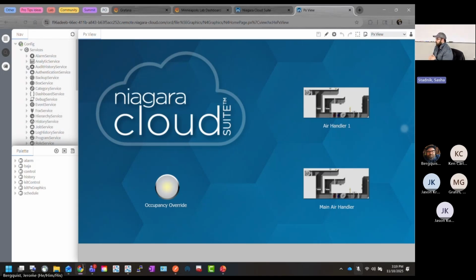So if we've got a site with 30 devices on this same network, we would have to add an RVM license to that supervisor and access it through a different web URL, because you can't jump to my supervisor saying 192.168.39.25 and then have my JACE be .26. So for RVM, that's going to be a different URL, a different port. I'll tell you, on the backside it's the same connector, but the actual user interface is different.